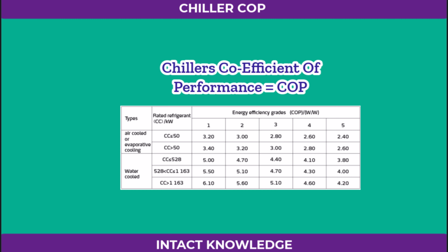Chiller manufacturers usually mention the rated COP in their technical documentation. We can compare this rated value with our calculated COP to assess how well the chiller is performing. A COP value between 4 and 7 generally indicates good performance.